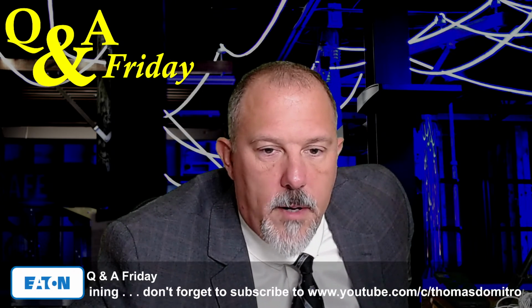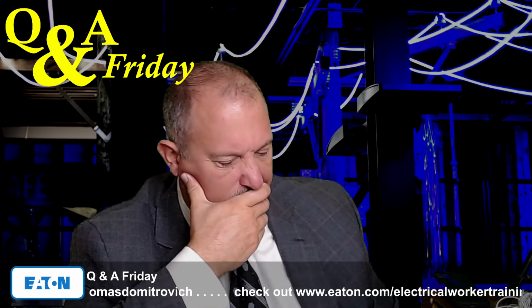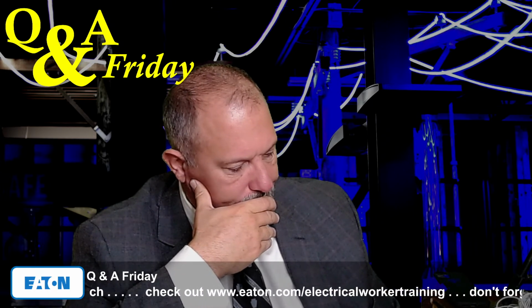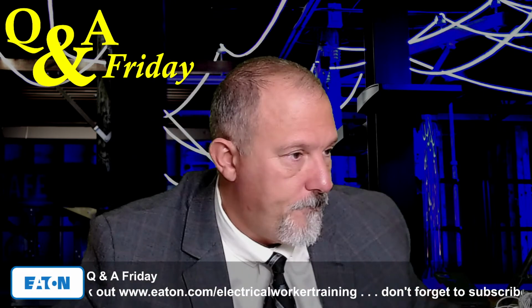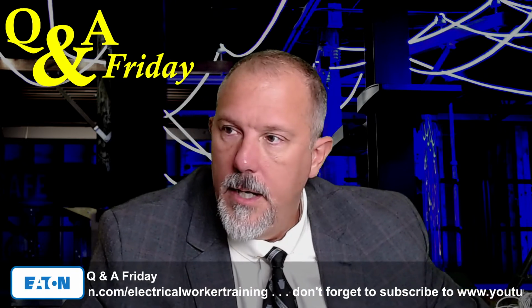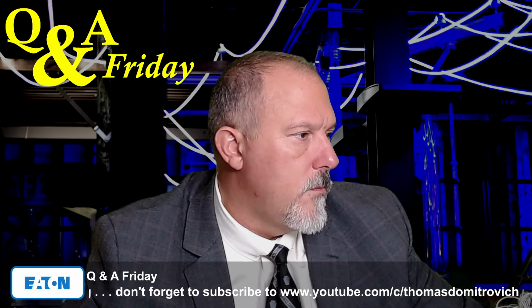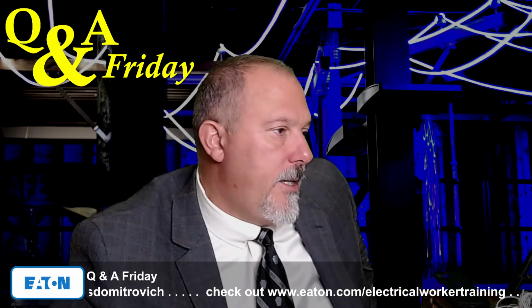In the graphics you show where motor fault current contribution affects adjacent circuit breakers fault current, I don't see how 240.86(C) is written properly. Motor contribution. So 240.86(C), we're talking interrupting ratings, right? So that's basics, and I go to interrupting ratings, and we'll just call that slide up just to see. I know which part you're talking about, which I don't have.